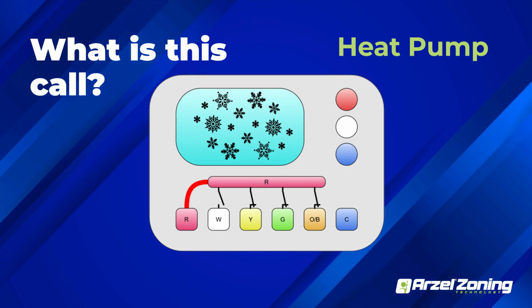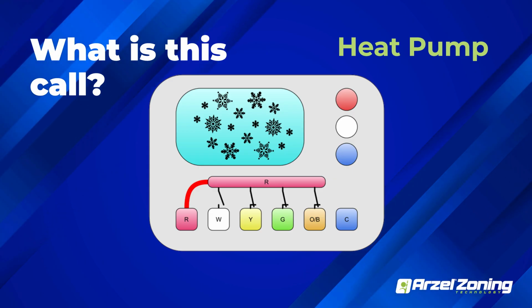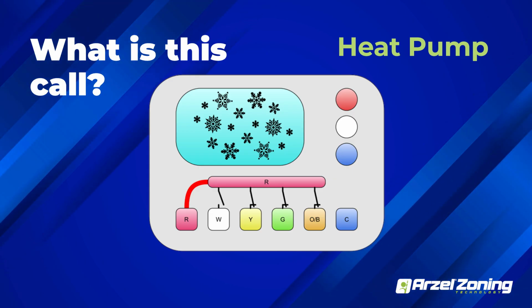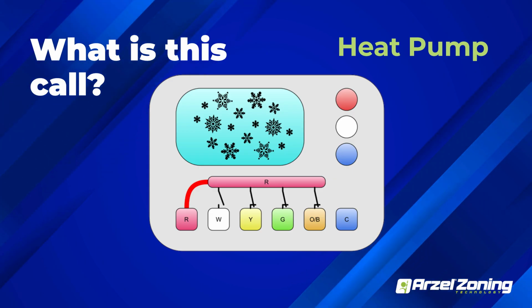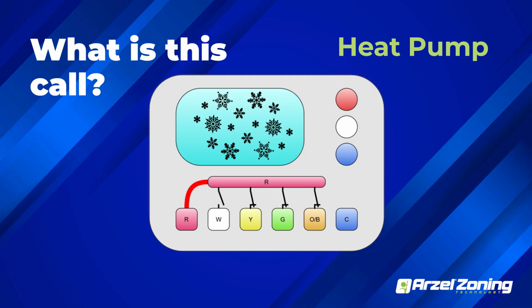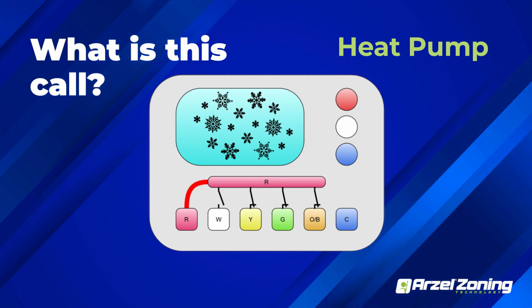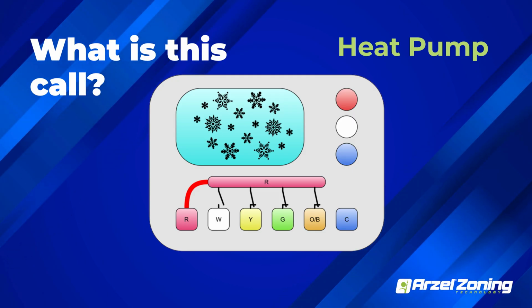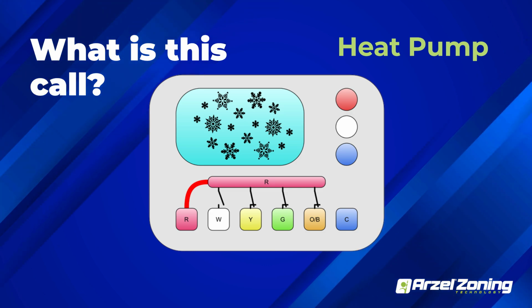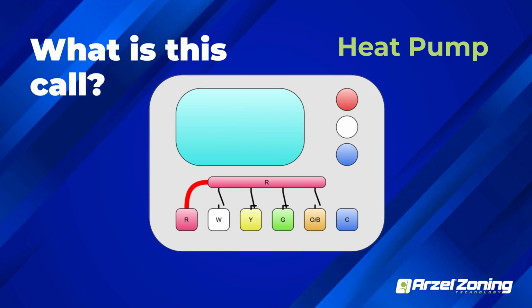So when I look at this thermostat call and I think about the Arzel panel, the O/B terminal is closed, that has to be a call for cooling from the thermostat, because the Arzel panel is what controls your reversing valve. So then when I look at the reverse of that, my reversing valve terminal is open now. I know that's a call for heat.